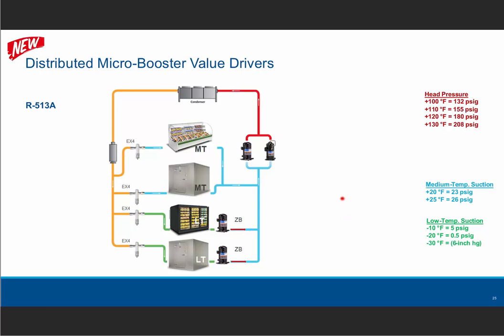So this is just a simple schematic showing the architecture a little more organized, if you will, where you have two or three compressors in parallel, medium temp, one digital, discharging into, of course, your outdoor condenser. And you can see that your liquid line in yellow or orange goes into your receiver, electronic valve, medium temp, case, light blue is suction. I've got a walk-in box, light blue suction.